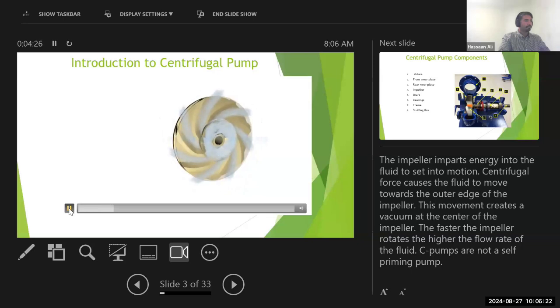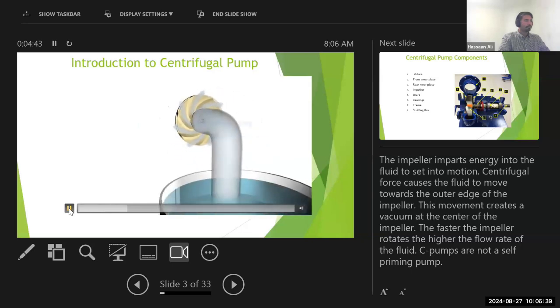Since rotational mechanical energy is transferred to the fluid, at the discharge side of the impeller, both pressure and kinetic energy of water will rise. At the suction side, water is getting displaced, so a negative pressure will be induced at the eye. Such low pressure helps in sucking a fresh water stream into the system again, and this process continues. This is the reason why priming is important for centrifugal pumps. If no water is present initially, the negative pressure developed by rotating air at the eye of the impeller will be negligibly small to suck a fresh stream of water.